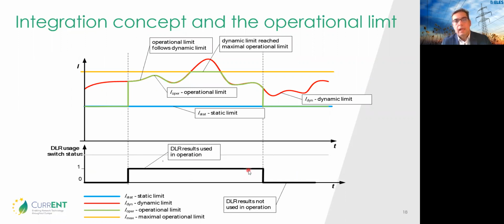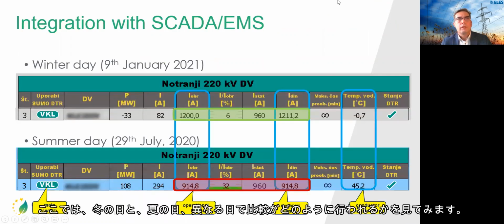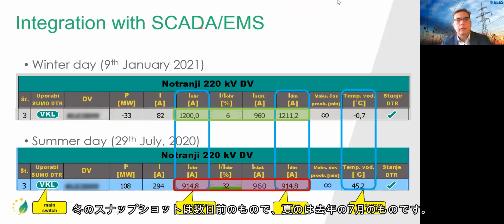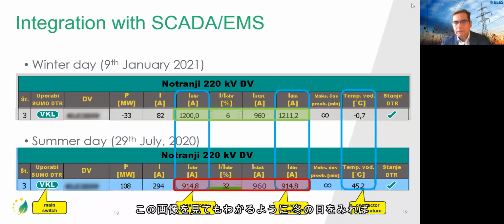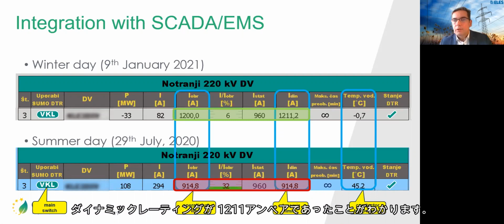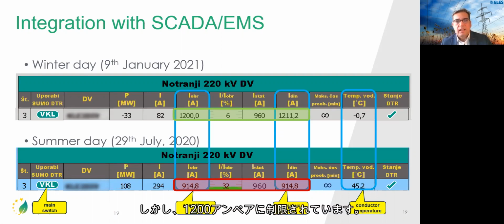Now, if we go to the next slide, we'll see a comparison for two different days. One is a winter day, the snapshot taken a few days ago, and the other is a summer day last July. As you can see from this image, on the winter day the dynamic value was 1211 amperes, but as it is limited to 1200 amperes, the operational limit is 1200 amperes. I'd also like to mention that the static value for this power line is 960 amperes.